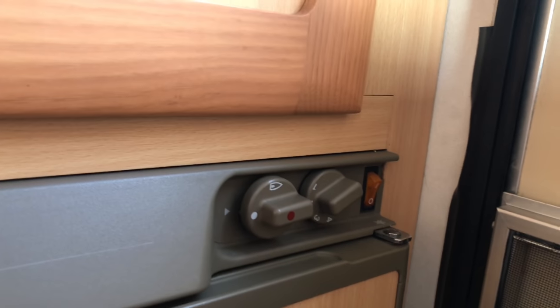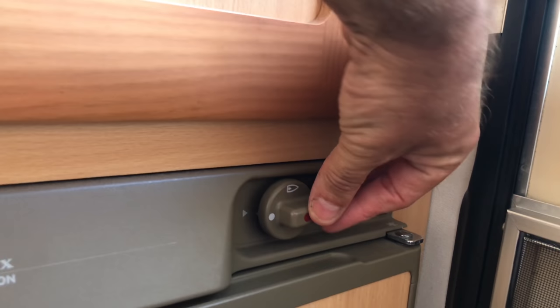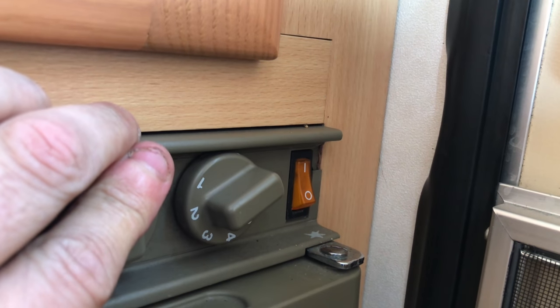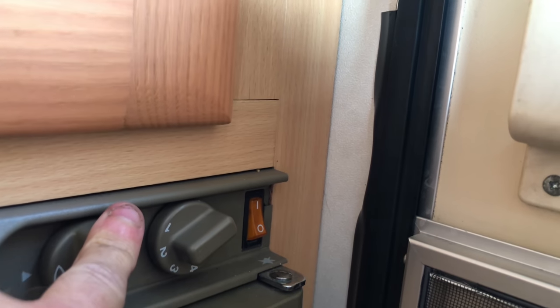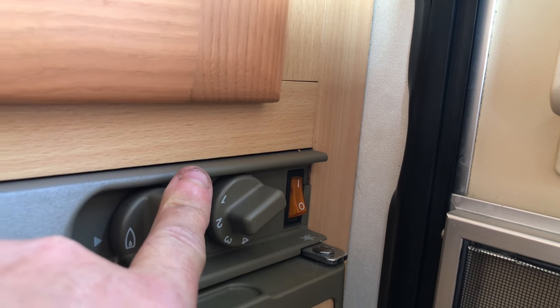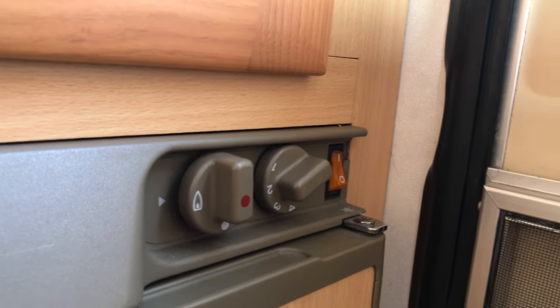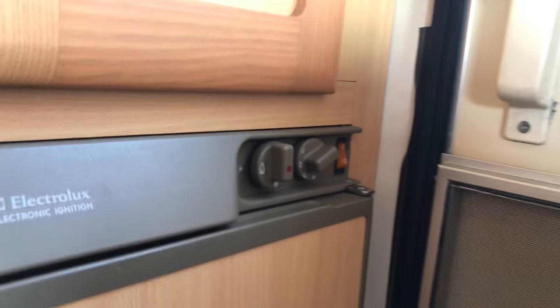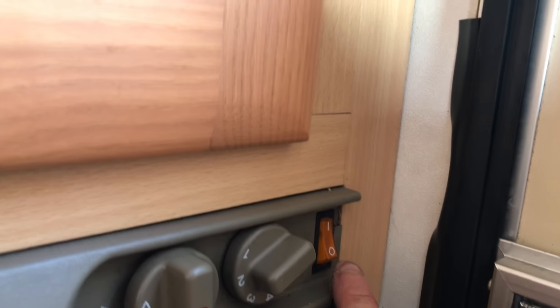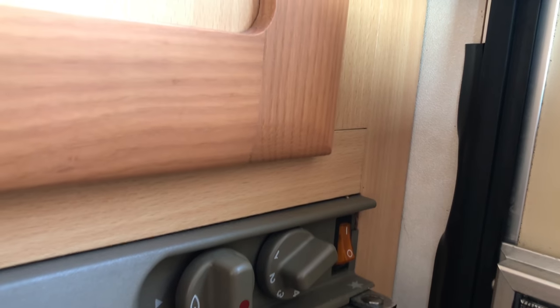So another piece of advice here. We're just going to put the sparker on. We push it down and over to the gas. When it stops sparking, that means that the pilot has taken. We are still going to be holding down the gas pilot about 5 seconds, then release. That means the pilot light has stayed open, as the sparker is not. Just one important piece of information: a lot of people think once it's sparked, they switch it off. It's a safety device, so that should stay in the on position.